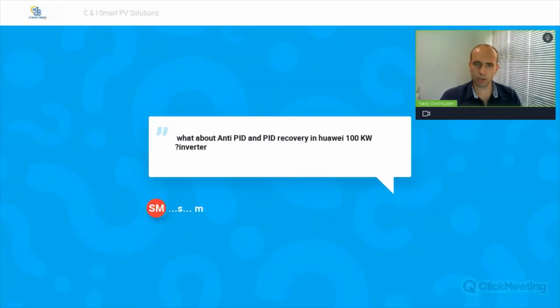So the first question that I've got here, I'm not sure if that was the first one: what about AntiPID and PID recovery in Huawei 100 kilowatt inverters? On a 100 kilowatt inverter, it's not a built-in function. Unfortunately, on a 100 kilowatt inverter, you do need to buy the Huawei SACU 2000D, which is the AntiPID. On the Huawei SACU 2000D, you can also have your smart logger built into that. So please note on the 100 kTL, PID is not supported or built in. If you're unsure about what inverter is supported, please just reach out to us and we can confirm that for you. But to answer your question, the 100 kilowatt doesn't have built-in PID.